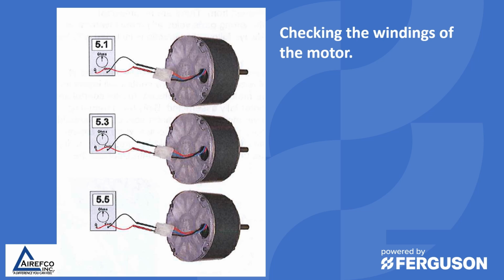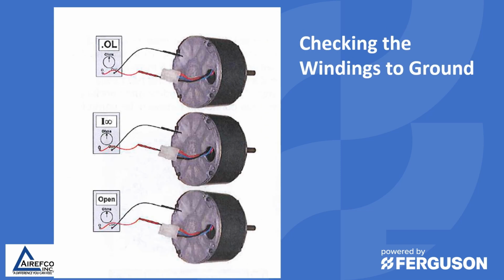But in this slide, we're showing you how to take the winding readings of the motor. You do this just like you would take ohm readings of the windings of a compressor, by taking the 3 leads coming out of the motor itself and checking the ohm reading of each winding. The second check is just like taking a winding resistance to ground on a compressor. Taking a resistance reading from each of the leads to a ground will tell you whether the windings of the ECM motor are grounded or not. You should get an infinity reading, absolutely no continuity between the motor lead and the ground.